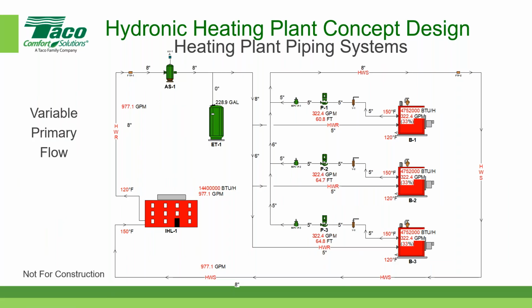Because the amount of space that the boiler plant will take up depends on some of the early decisions that you make. In other words, you may need 10% more space in your mechanical room based on the number of boilers that you choose, but you may be giving up efficiency. So before you go down the road of determining how much physical space you should need, you should try to get your hands around the proper configuration for the number of boilers, percentage of load, temperatures, and redundancy.